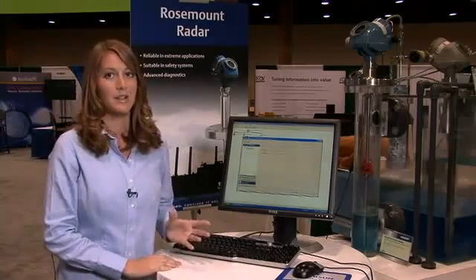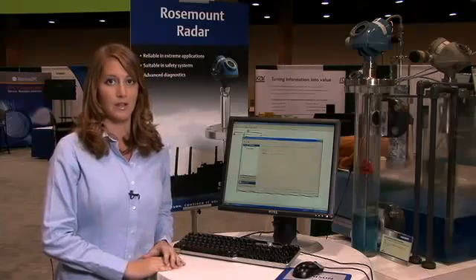Currently we have this red cable that is representing the build up on the probe. But we're going to remove this and show what a clean probe would look like with signal quality.